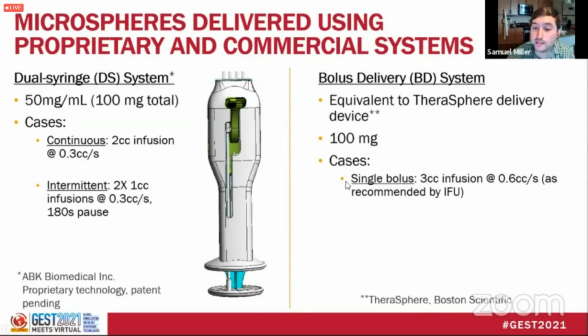So we just tested the 3cc infusion. That essentially delivered almost entirely this 100 milligram committed dose, if you will. And then afterwards, we waited and measured the flow rates after a long period of time. We waited at least 5 minutes and up to 10. Essentially, we waited till we no longer saw a change in the flow rates that were measured.